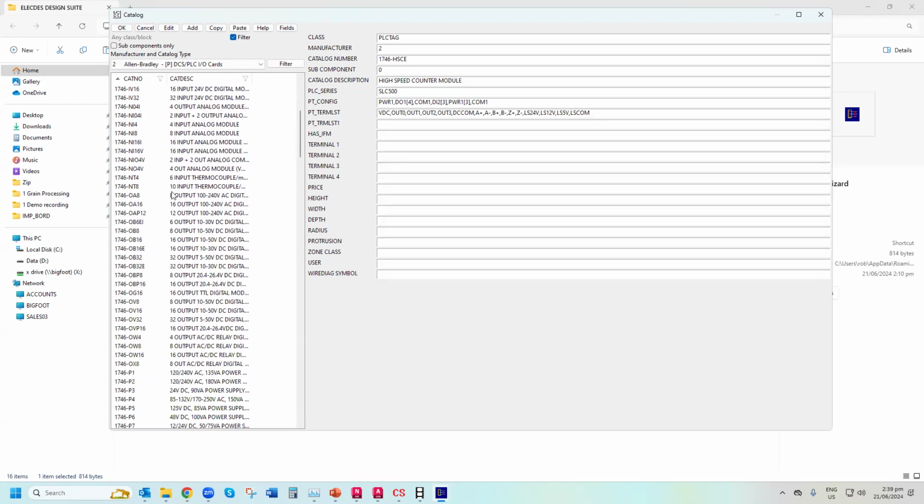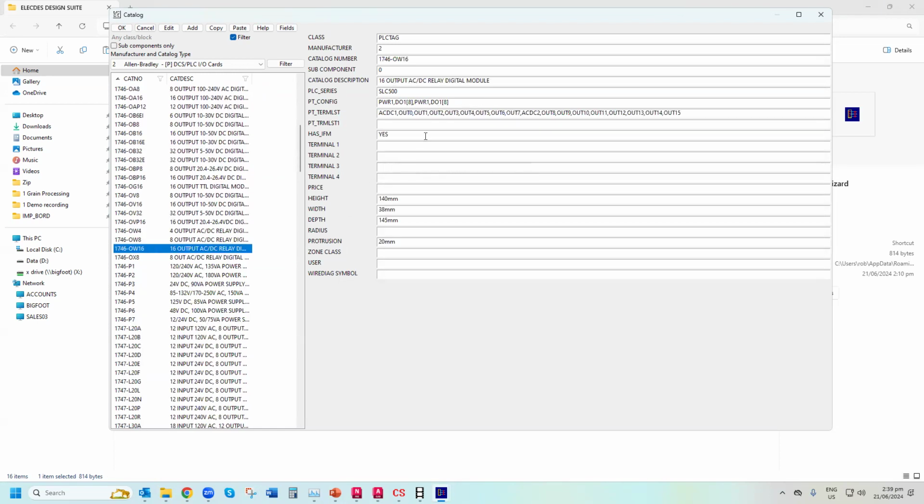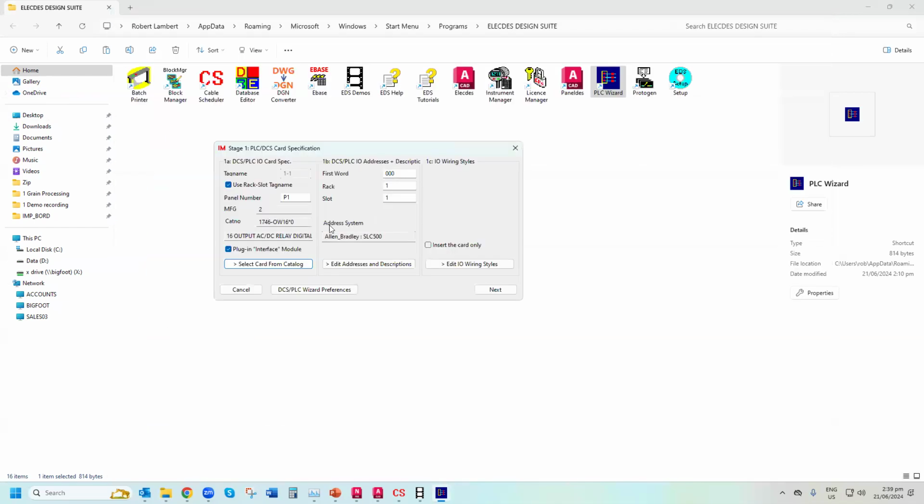Okay, so if I have a look at my 1746-OW16, the important things to note are the terminal configuration. I've got one power 8 digital outputs, one power 8 digital outputs, and the actual terminal numbers which correspond to the things above. Okay, so again, you want to group, if I look at a 32 output card, that one's got two power 16 outputs, two commons. I could group everything together. It's flexible in terms of how you stack things together, if you like. But I'll stick to this 1746-OW16 because it's not too big.